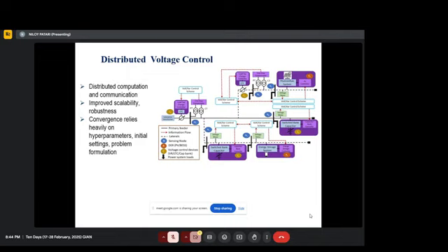That set point can be, suppose three banks were on. Each capacitor bank was say 100 kVr, so initially it was giving 300 kVr. If the set point says to switch off one bank, then now you're giving 200 kVr, right?